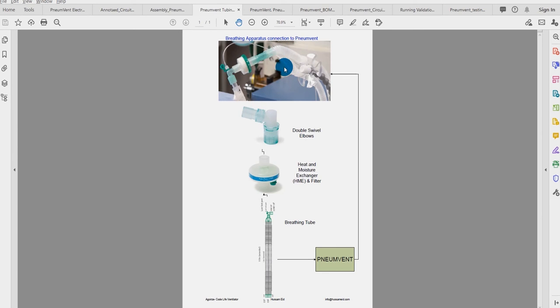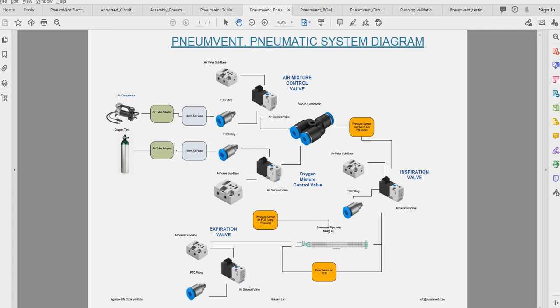So the patient essentially is tubed in here and is going to go through the system. This tube, the small tube here, goes to the flow sensor. And everything will be essentially modular at this stage, so everything can be taken care of. If you want to clean this, or remove it after each patient, you simply disconnect these and throw them in the garbage, or use whatever sterilization method a hospital might use. But this is what I would consider the hygienic standard for replacement.